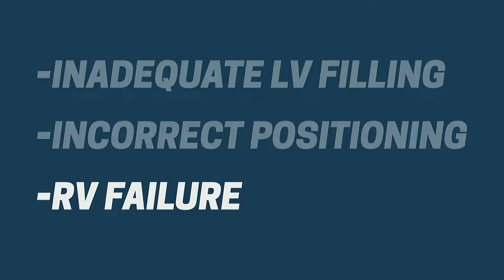So let's make this simple. Let's go ahead and fix these suction alarms. First thing, as the machine said, reduce the P level. Okay, simple enough. Do your echo, check the filling pressures and your volume status on your patient. You might need to do a small fluid challenge to see if there's any change, then go ahead and do so. And you might need to reposition the device.